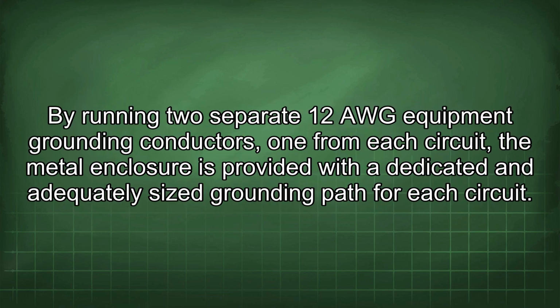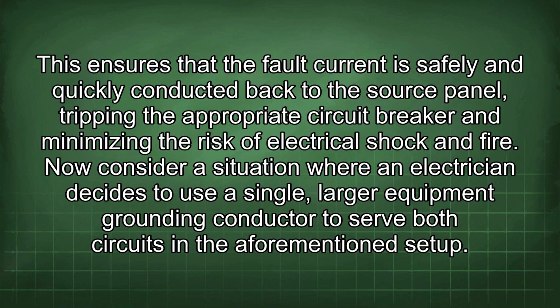By running two separate 12 AWG equipment grounding conductors, one from each circuit, the metal enclosure is provided with a dedicated and adequately sized grounding path for each circuit. This ensures that the fault current is safely and quickly conducted back to the source panel, tripping the appropriate circuit breaker and minimizing the risk of electrical shock and fire.